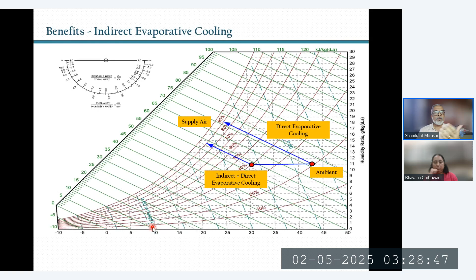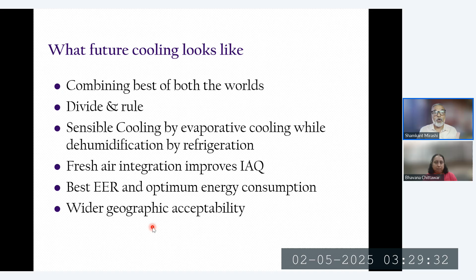The first application is essentially in evaporative cooling or air cooling technologies. We are saying that the same technology will be applicable when we talk about air conditioning, right? When we talk about air conditioning, essentially we talk about sensible cooling and latent cooling. When we throw this air on the chilled water coil, we drop the temperature and then we remove the moisture, right? That's how the typical curve is. I have it in a subsequent slide. Today, the same refrigeration coil is removing temperature as well as moisture, and those who are well versed with HVAC will be aware that the fresh air loads are almost 3 times higher than the recirculation, and that's another set of problems we foresee. So this could be a typical scenario.